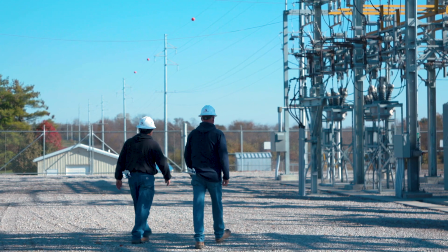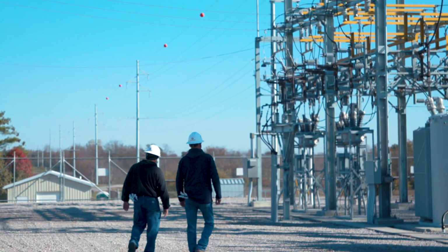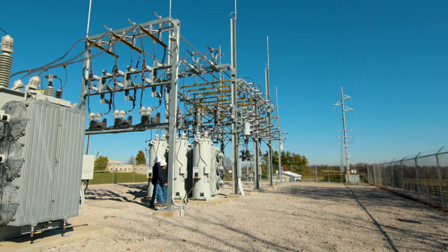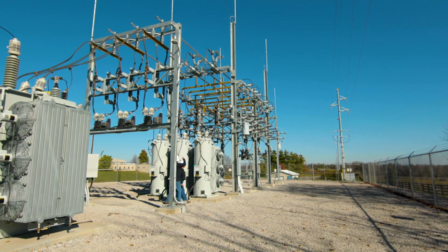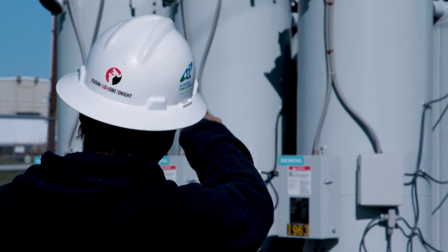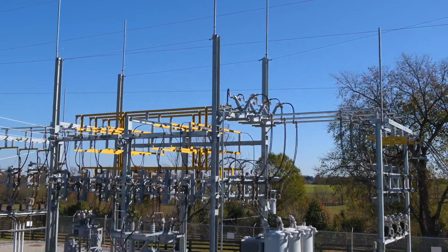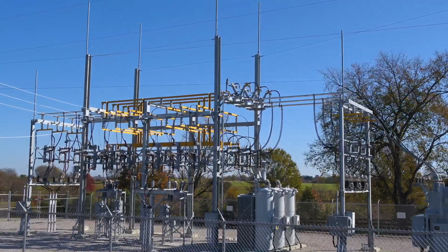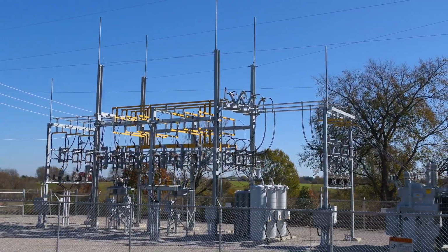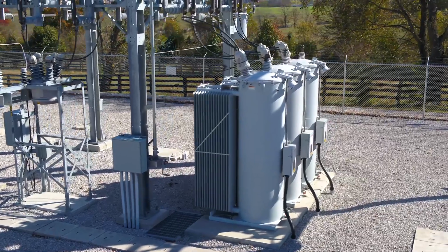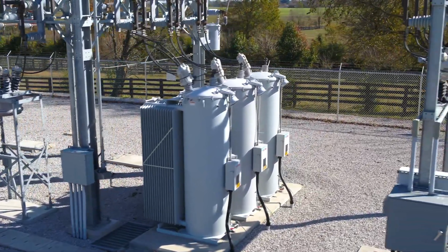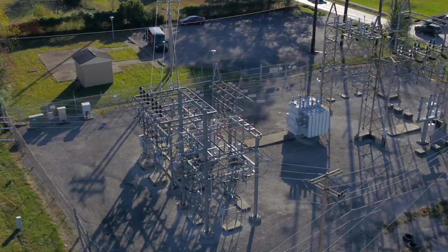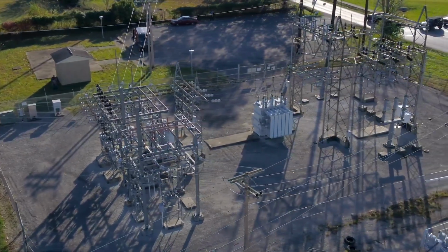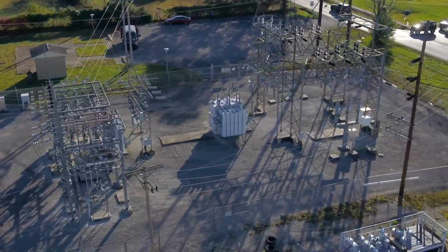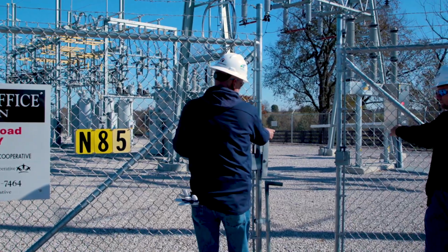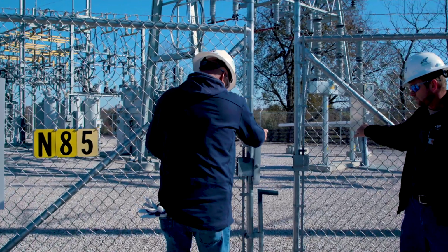If equipment appears burned, it is likely that the parts of the regulator have weakened. Most of the problems with regulator malfunctions can be tied to motor capacitors that have failed. The second most common problem involves position switches inside that have gone bad. Always remember that low tapping, clicking, and clunking sounds are normal. But if you are concerned about what you are seeing or hearing inside a substation, immediately evacuate and report the situation to the EKP dispatcher.